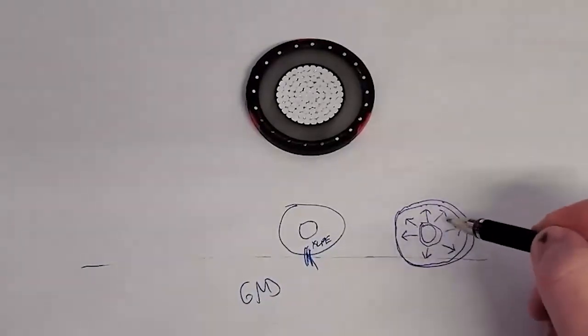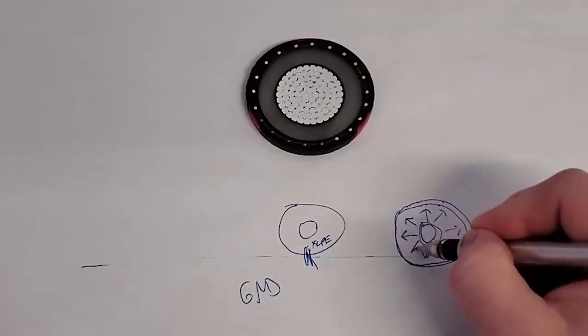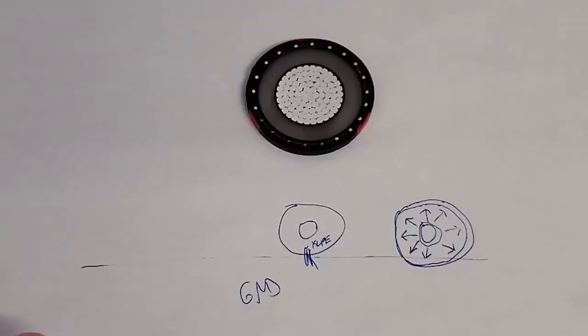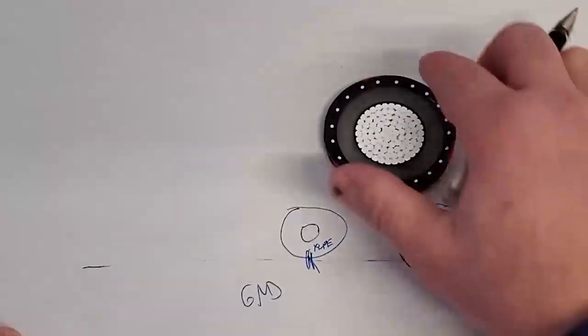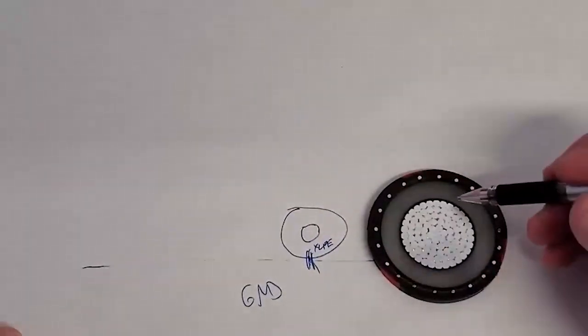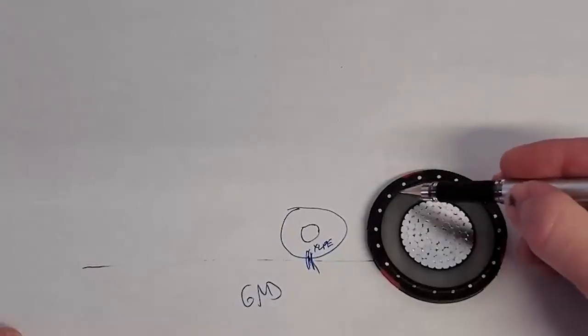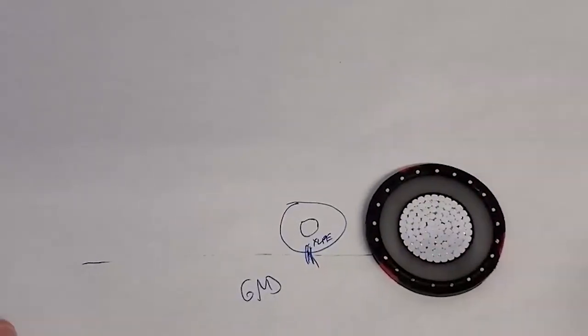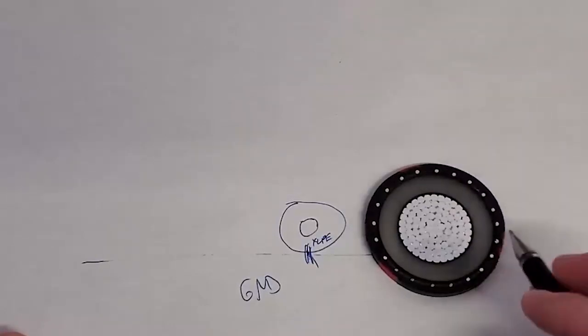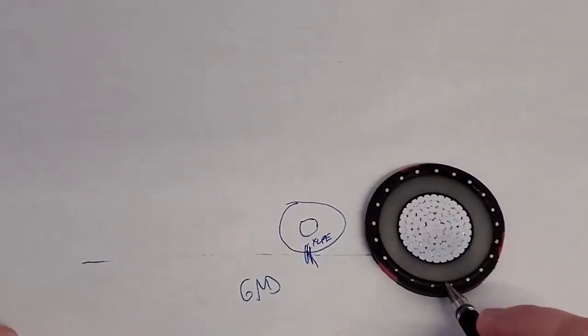And what this does is allow even breakdown of the insulation over time. And when I say over time, we're talking 20 years at a minimum. That's typically the life of this cable. It actually lasts up to 40, 50 years even. And there's some cable out there that lasts even longer. The main reason for that is the even distribution of flux through the insulation to that semicon and to the ground. So that's the main reason why. And we just talked about the insulation shield.